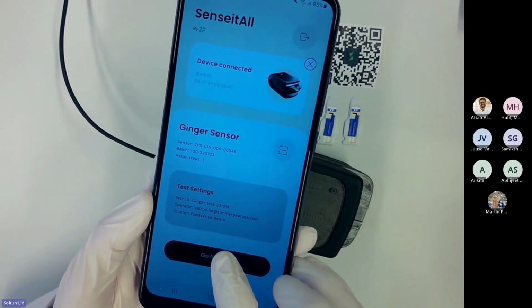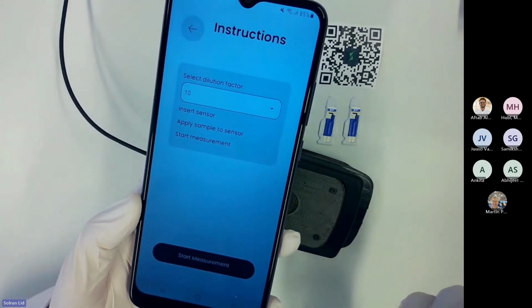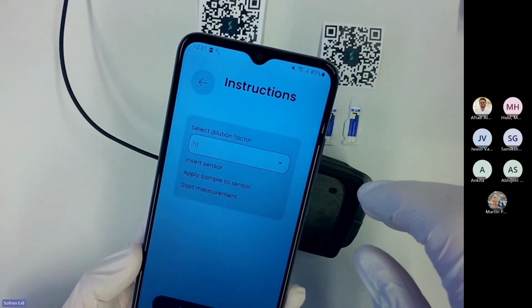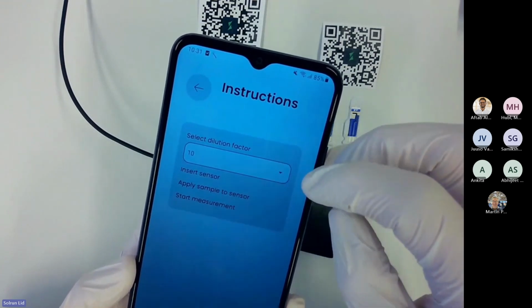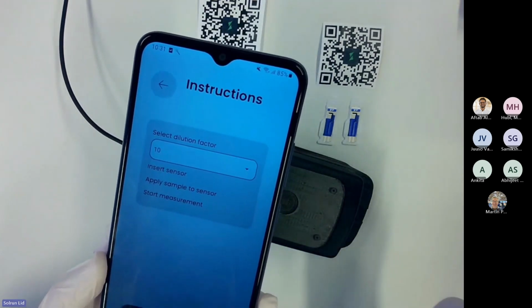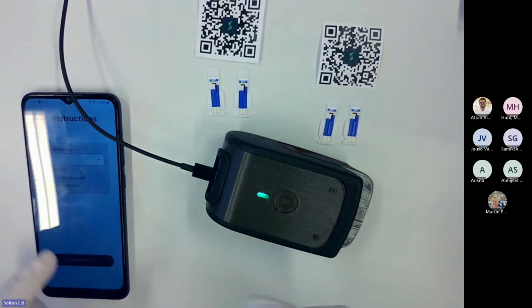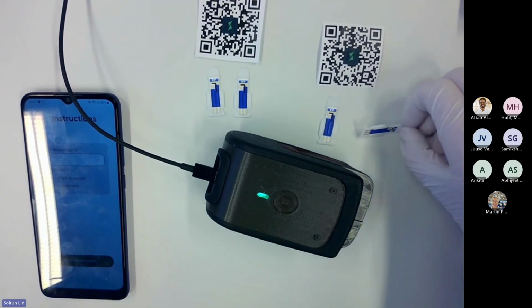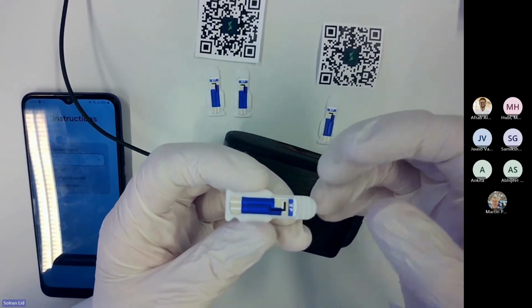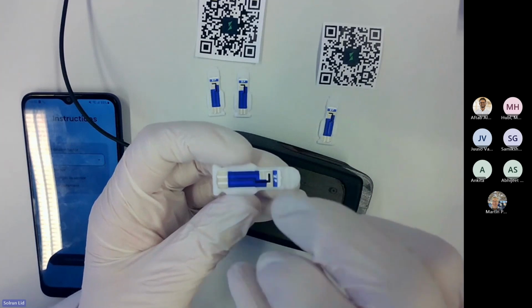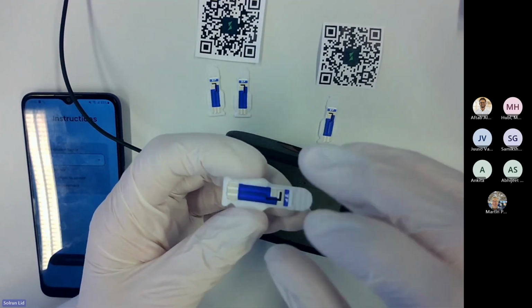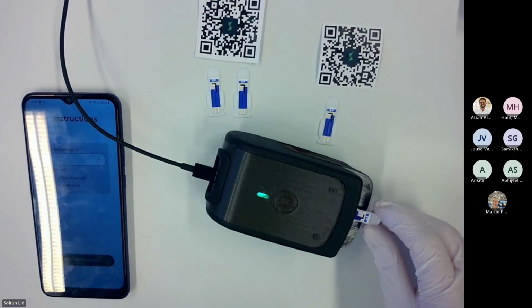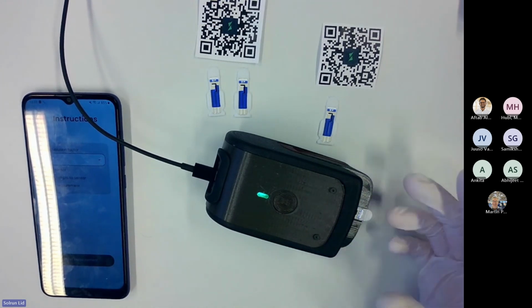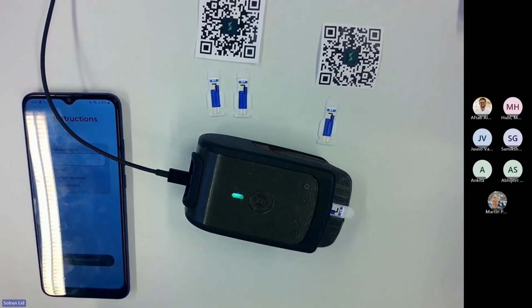So I will click go to assay, and it takes me to instructions. Here I have to decide what dilution factor I'm using, and for this sample in particular, we're using a 1:10 ratio. So the screen tells you what to do. We will insert the ginger sensor, and we have these cartridges around the sensor just so that it's easier for us not to touch the electrodes of the sensor. So stay away from the electrodes, do not scratch it, just keep it contained. We'll just insert the sensor just like that, and push the device up so that we have a connection.